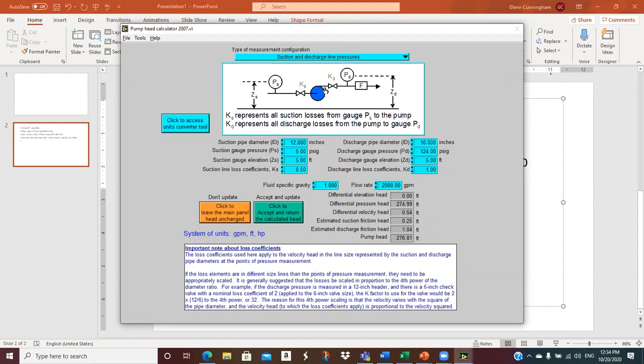Likewise, you have the opportunity to put in some loss coefficients from the discharge of the pump to the gauge, because there could be some losses in there. If you don't put that in, the pump is actually putting out more pressure here than you're measuring here, and you're shortchanging the pump. This would be a flow measurement, and then we have elevation, say from some datum, usually the floor or the ground, if there's a difference in heights of the gauges.